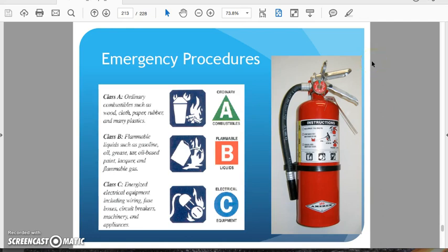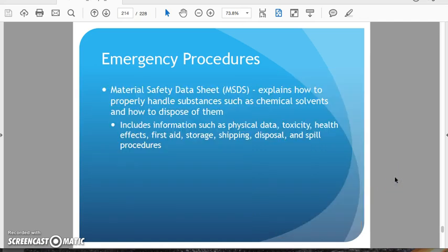Fire extinguishers, they remind you that we're dealing with a lot of electrical things, so the extinguishers around our area should be rated as C for dealing with electrical fires, but you're going to find probably most of the stuff you encounter is ABC. A is your ordinary, like paper, wood, combustible material. B is your liquids, like your greases and those sorts of things that you'd have in a kitchen. But C is the electrical. So most of the stuff we encounter needs to be C rating on the fire extinguisher at least. But you're going to find most things are A, B, C.